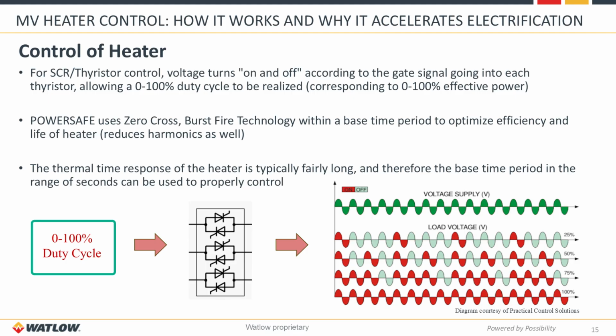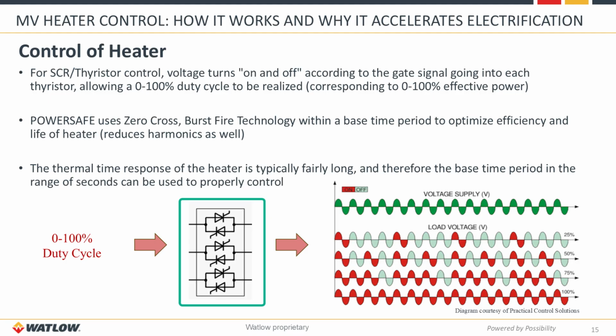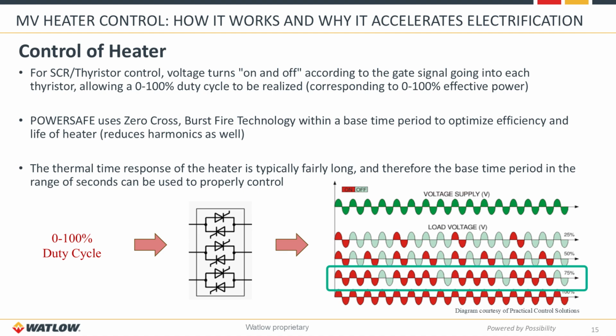Typically, you can do that through a 4 to 20 milliamp type input signal. We convert that to a 75% firing rate through the SCRs and thyristors right here. And then you get an output pattern similar to this one that I'm showing right here. The burst fire, again, spreads that out so that you're firing along the entire period of the system here. And the zero cross technology ensures that you're only switching this at the zero cross of the sinusoidal wave.